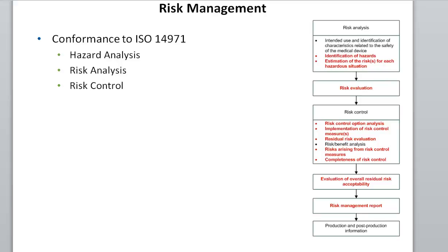So this is one key distinction between the top-down approach to risk management and how some companies are doing FMEA from bottom up. FMEA often talks about severity, occurrence, and the detection or probability of detecting a problem or detecting the risk. The top-down approach doesn't care about detectability. It assumes the end user has no ability to detect there's a problem because you never know what kind of state the patient is in.